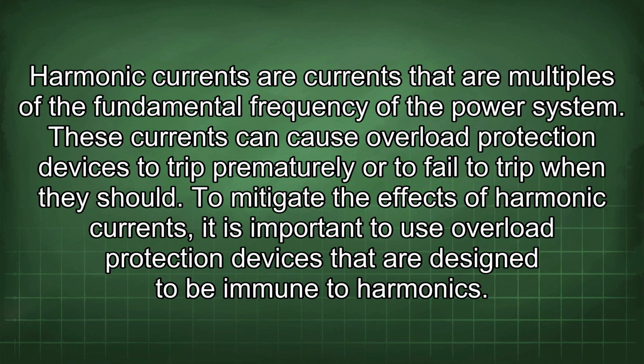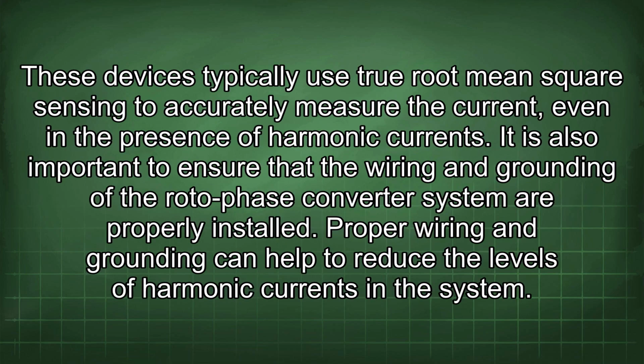Harmonic currents are currents that are multiples of the fundamental frequency of the power system. These currents can cause overload protection devices to trip prematurely or to fail to trip when they should. To mitigate the effects of harmonic currents, it is important to use overload protection devices that are designed to be immune to harmonics. These devices typically use true root mean square sensing to accurately measure the current, even in the presence of harmonic currents. It is also important to ensure that the wiring and grounding of the roto-phase converter system are properly installed. Proper wiring and grounding can help to reduce the levels of harmonic currents in the system.